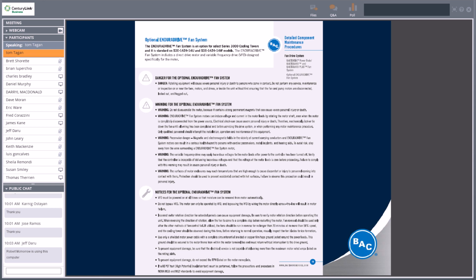We're going to skip over the gear, which we'll get to in a second, but BAC has also come out with a direct drive. They have an agreement with Baldor for this specific tower, the Series 3000, and I believe it's 25 horsepower and above. We can now provide a direct drive fan motor. What that does is eliminate any belts, any gear, and the additional oiling or lubrication of those bearings. Those additional failures get taken out of the picture.